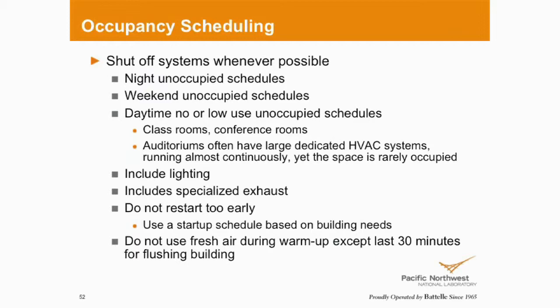Specialized exhaust systems, we see a lot of exhaust systems. Bathrooms, general exhaust systems running with no one in the building. So if I'm shutting off my regular air handling units, but my exhaust fans are running, what's that mean to my building? Negative. Whew, not good. Really cold outside, I don't want to be negative. Really hot and humid outside, I don't want to be negative.